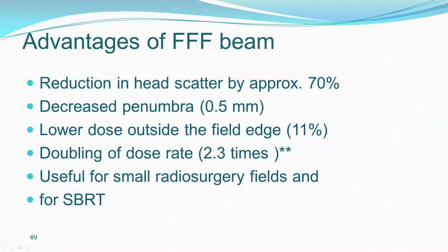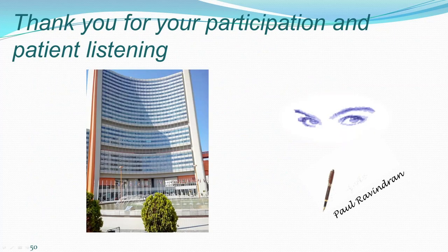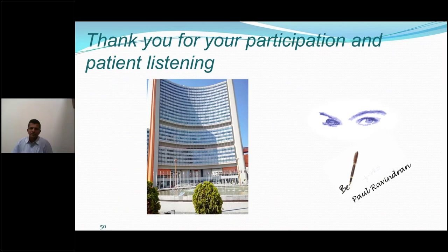The advantages of Triple F beam: reduction in head scatter of about 70%, decreased penumbra, lower dose outside the field edge, doubling of dose rate, and it is useful for small radiosurgery fields and SBRT. It can also be used for IMRS and IMRT. Thank you very much for your patient listening. If you have any doubts, I would be happy to share.